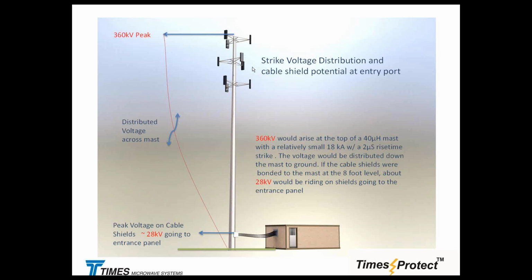Now a graphic representation of what will happen with a total mast inductance of 40 microhenries and a relatively small 18 kiloampere peak strike, which has a 2 microsecond rate of rise time. So the di/dt of that strike was in the range of 2 microseconds. We had 18,000 amperes peak, and the inductance of that mast monopole was in the range of 40 microhenries. The inductive voltage drop calculated at this point is 360 kilovolts peak.